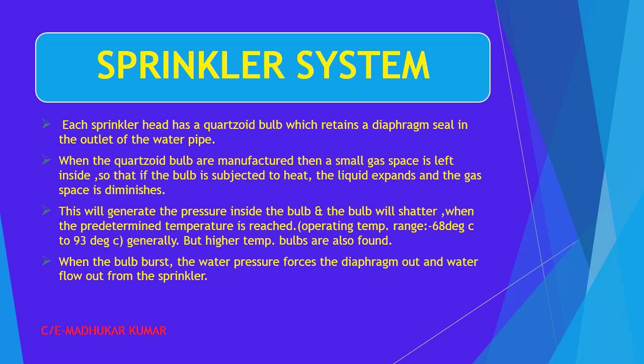Okay, so when we talk about the general operating range, it is 68 degrees centigrade to 93 degrees centigrade. Bulbs for higher temperatures are also found, and they are installed as per the space requirement. We will see that. Okay, when the bulb bursts, the water pressure forces the diaphragm out and the water flows out of the sprinkler. This is the main working part of the sprinkler head.